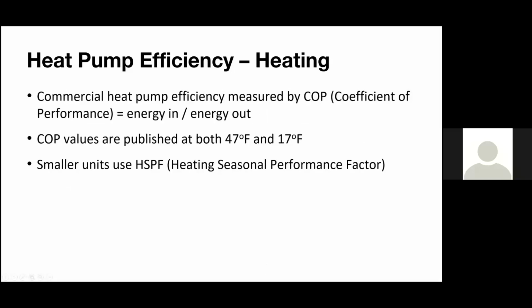So transferring over to the heating side of things, most commercial heat pumps, actually pretty much all commercial heat pumps, use COP as an efficiency metric. I know Adam's mentioned this a little bit, but that is the coefficient of performance, which is as simple as the energy out divided by the energy in, right? So Adam mentioned at lower temperatures, as it starts to drop, there is a derate associated with these heat pumps, which is fine. We still have a higher COP than other things that I'm going to talk about, but we do have a derate because it is a little bit harder to extract that heat out of low ambient air.